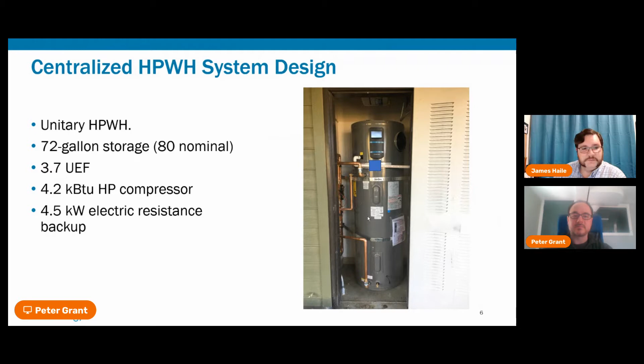The heat pump water heaters were monitored using BTU meters to monitor the hot water demand and a true RMS energy meter to monitor the electricity use. These devices calculated energy rates and totals many times per second, and both rates and totals were logged at 15-second intervals. Because we were doing load shifting, we needed to have a mixing valve so we didn't send scalding water to the fixtures, and because we really wanted the actual hot water draw data, not just the amount of hot water coming out of the tank, we put our BTU meter on the supply side of the mixing valve.